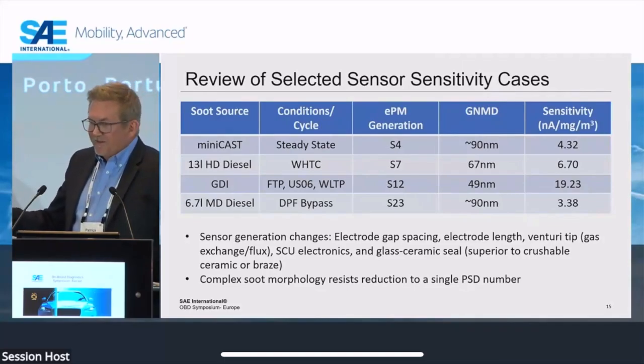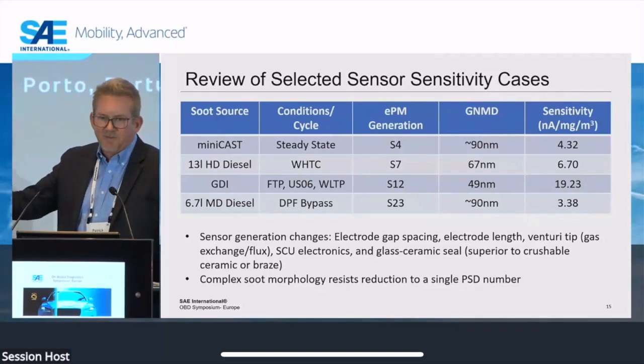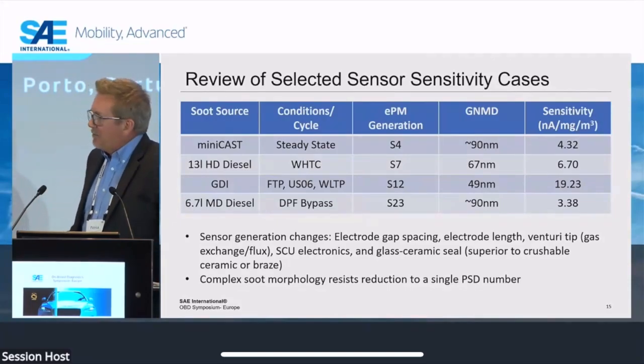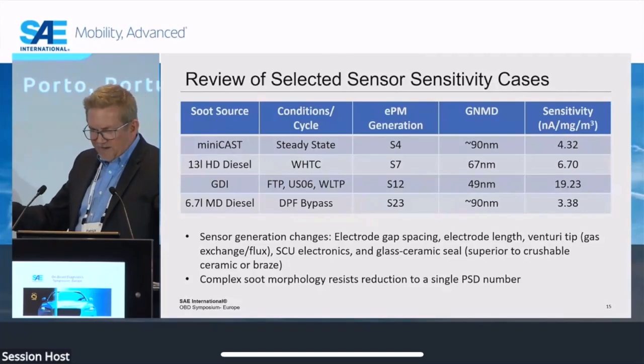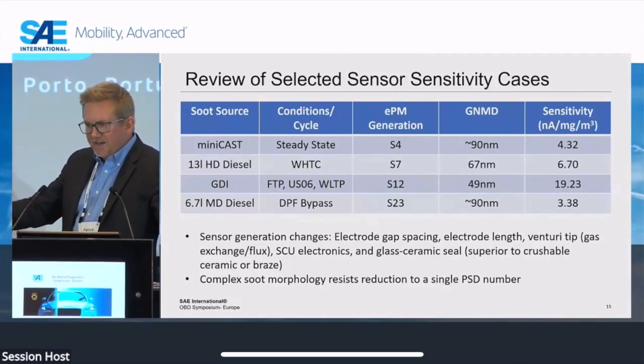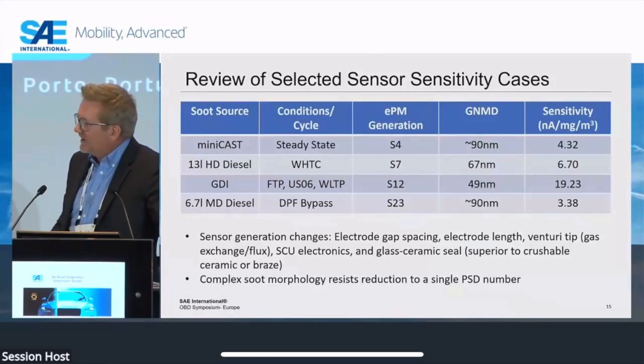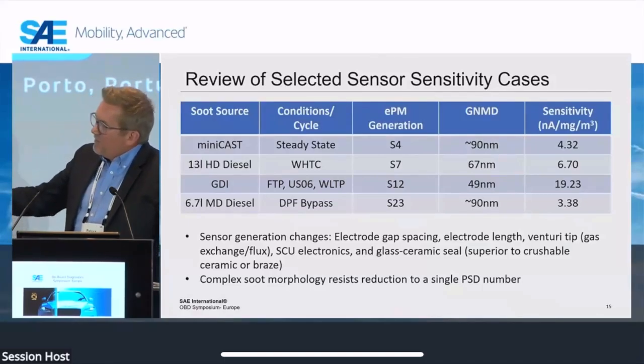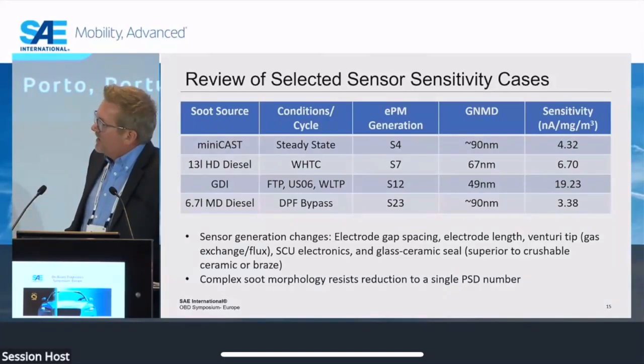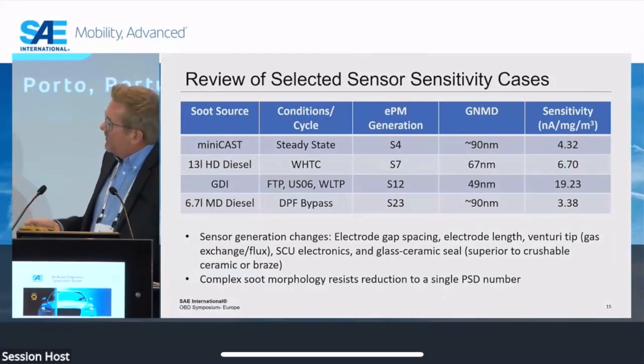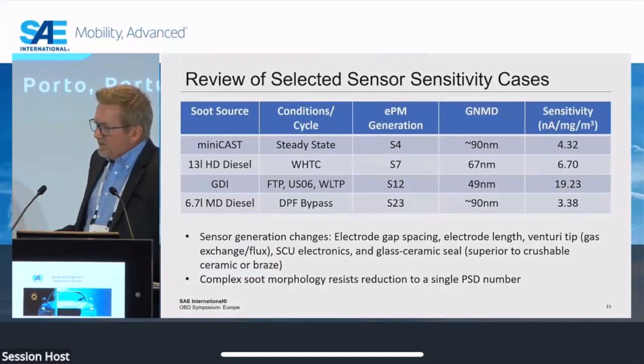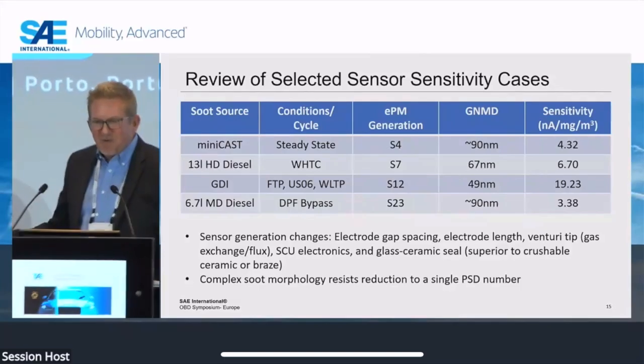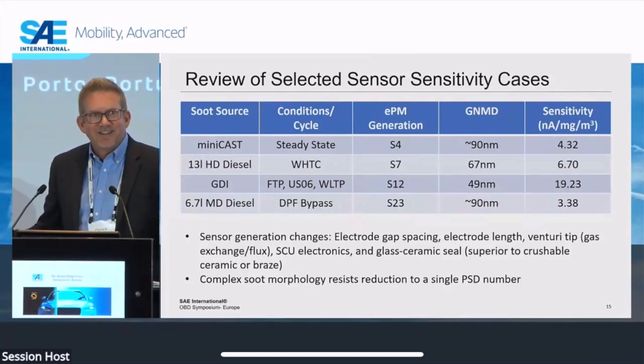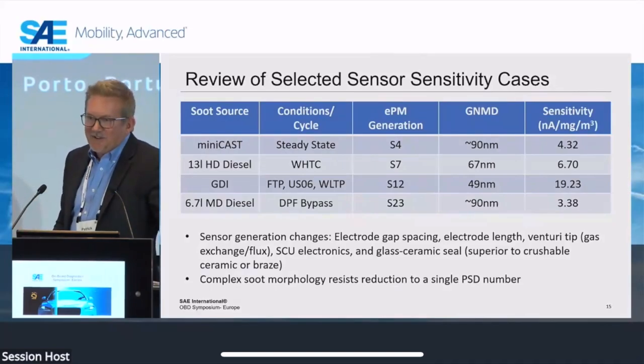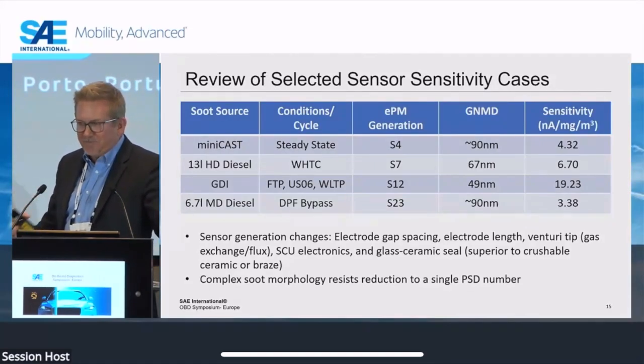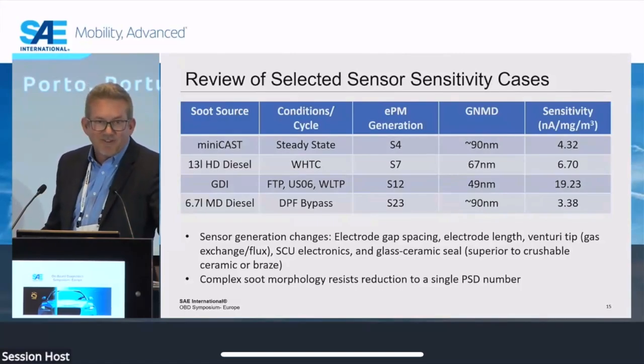The electronics themselves, there are different ways to create the high voltage, different ways to embody the ammeter. And then the seal, as one might imagine, having a really good electrically isolated, thermally isolated to some extent seal matters. Anyway, moving on with the chart, various different size distributions, and those are the different sensitivities we saw. So if there's one takeaway, it's that there's a relatively wide, not orders of magnitude, but relatively wide sensitivity range. And to maximize accuracy in a given application, you need to actually do some real work with the reference instrument.